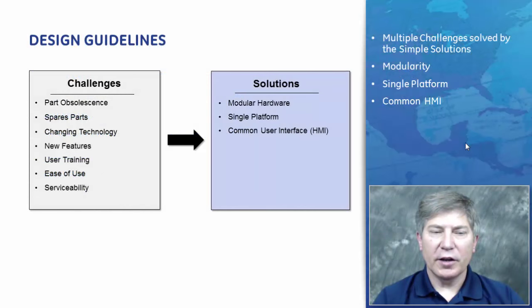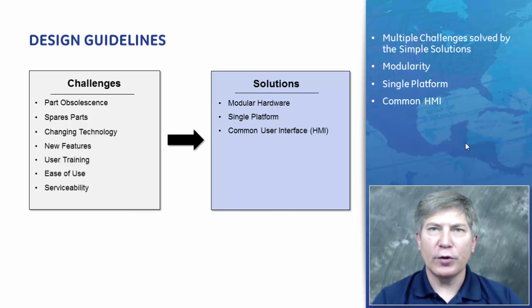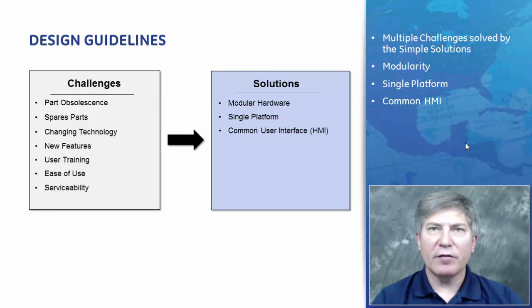When first designing the UR relay, multiple challenges were considered: part obsolescence, spare parts, constantly changing technology, adding new features, user training, ease of use, and serviceability. The solutions the design engineers arrived at were: making the hardware modular and common to all applications, a single platform with one firmware used on all UR relays, and a common user interface shared by all UR relays.